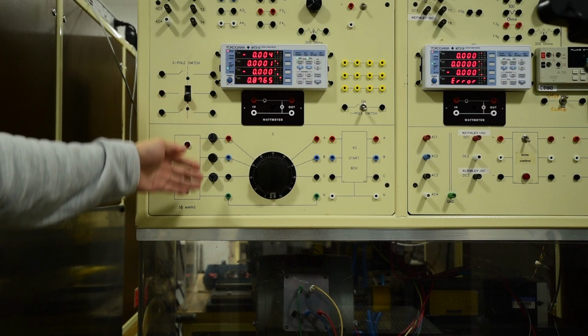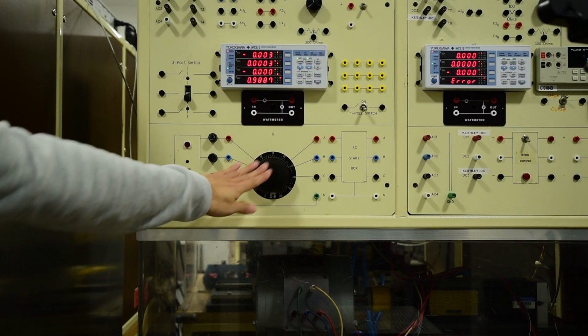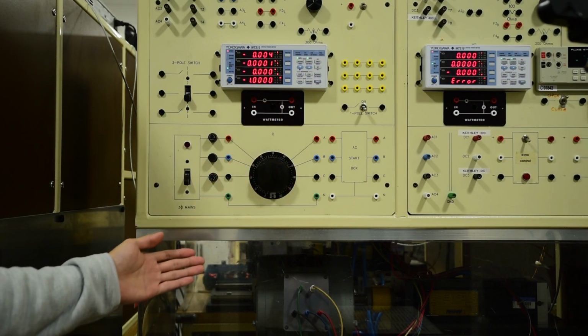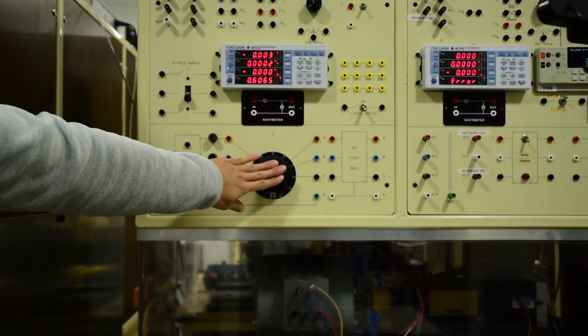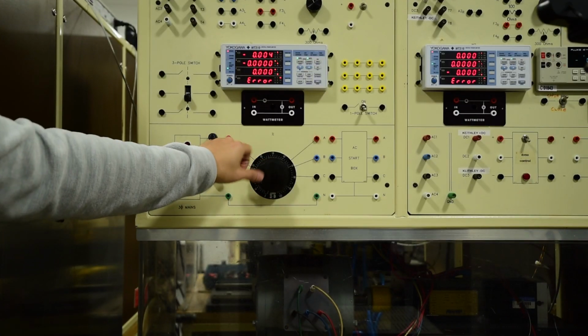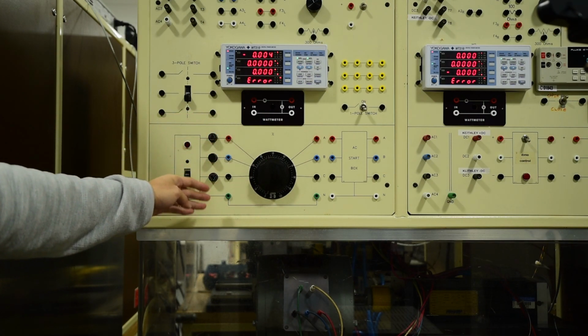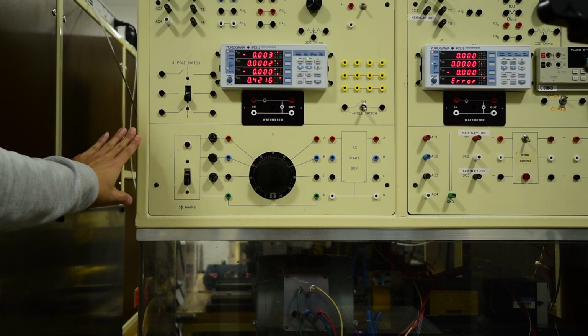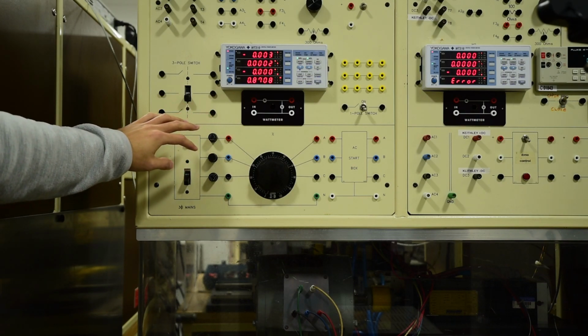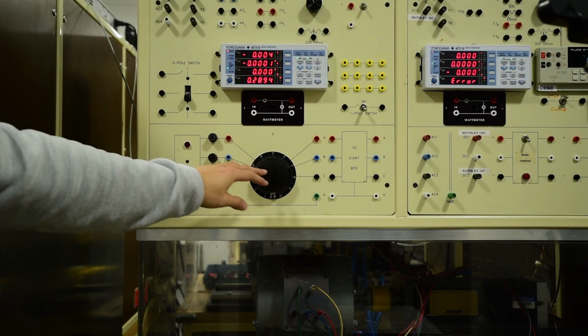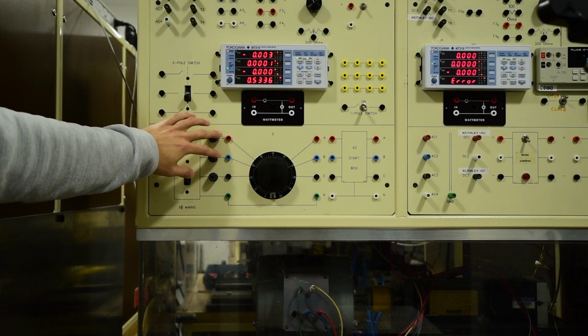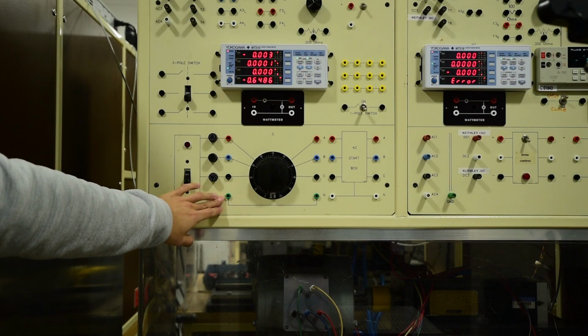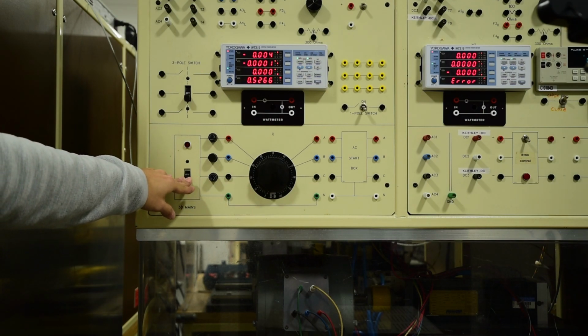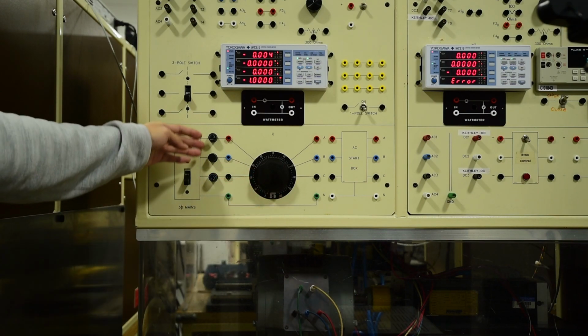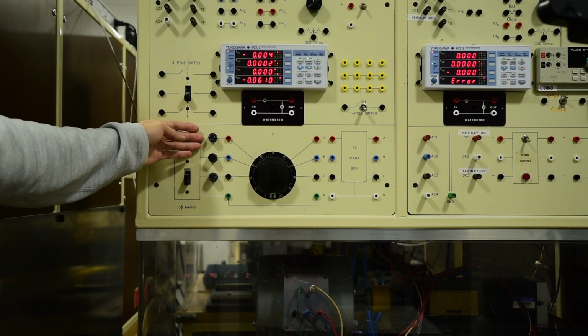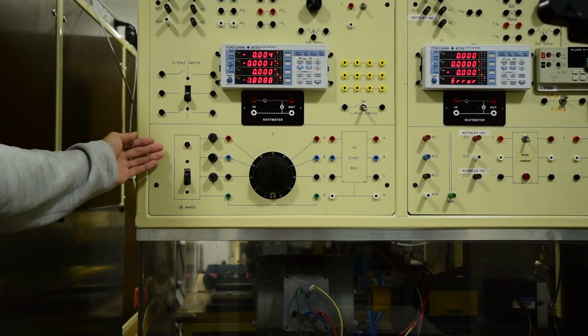There are 2 columns of connectors for this knob. On your right is what you usually need to use — those connect directly to this Variac, and the voltage will change as you turn the knob. The ones on the left are not connected to the Variac; they're directly connected to the 3-phase power, so you'll get 208 volt line-to-line voltage no matter where you turn the knob. So be careful, these terminals are powered when the switch is on, even if your knob is at 0.